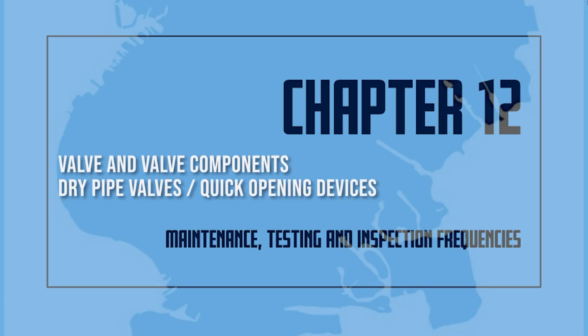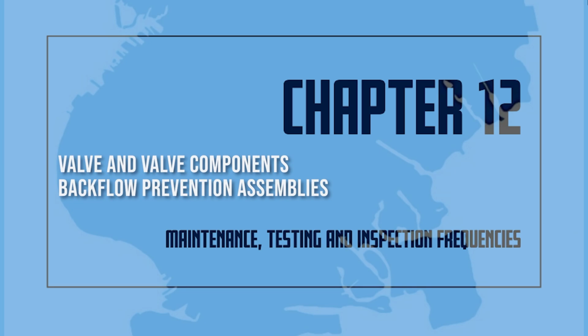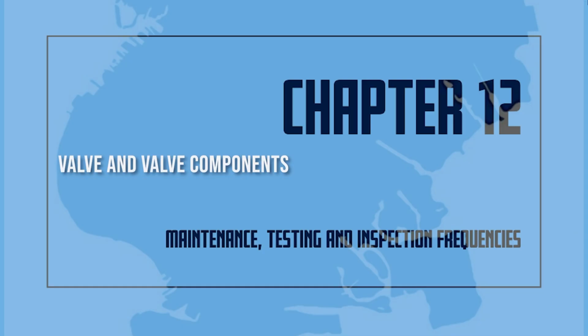Strainers, filters, restricted orifices, and diaphragm chambers shall be inspected internally every 5 years unless tests indicate a greater frequency is necessary. Backflow prevention assemblies. The double and single check assembly valves and double check detector assembly valves shall be inspected weekly to ensure that the O, S, and Y isolation valves are in the normal open position. Valves secured with locks or electrically supervised shall be inspected monthly. Fire department connections.